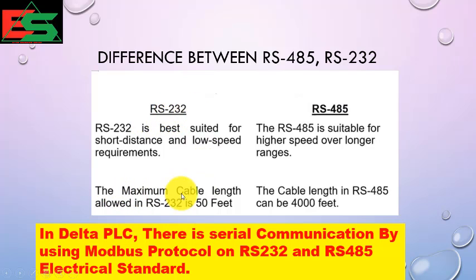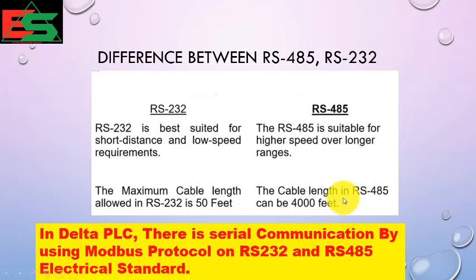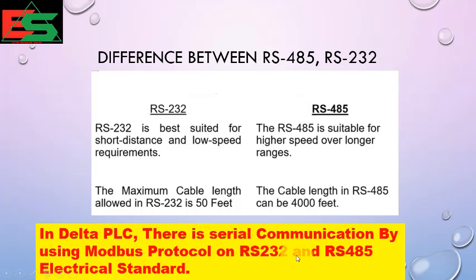The maximum cable length allowed for RS-232 is 50 feet. But in case of RS-485 the cable length is more than 4000 feet — it is a very long range communication standard. In Delta PLC, serial communication is done using Modbus protocol on both RS-232 and RS-485 electrical standards.